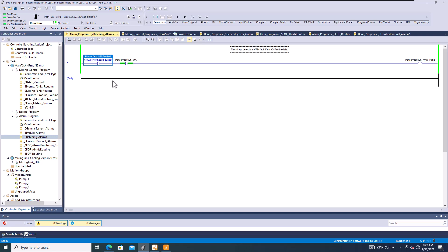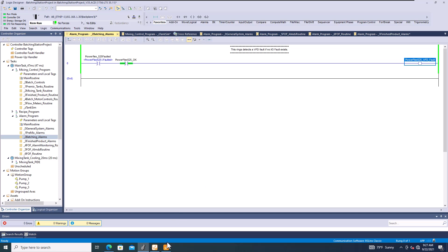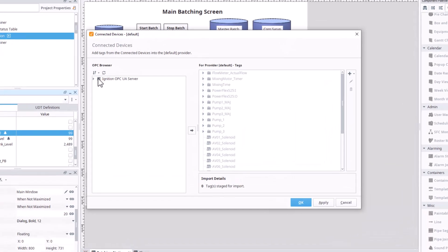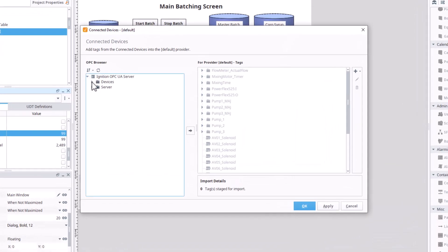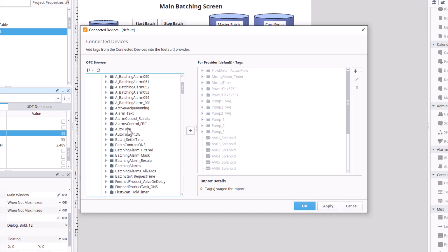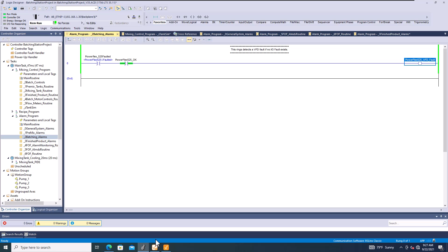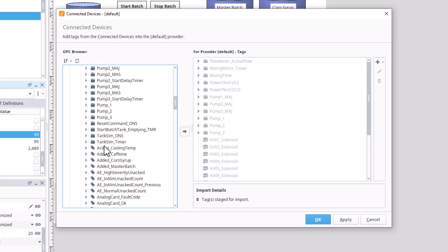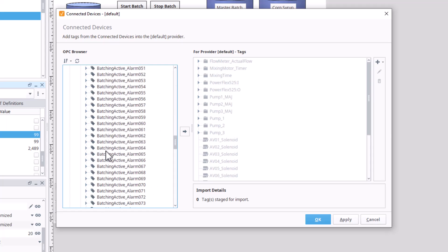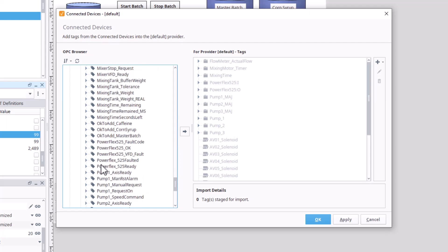Adding a drive fault alarm is just a matter of adding a tag. Browse to Ignition → our devices → batching station → global settings → batching alarms, and find the PowerFlex 525 VFD Fault tag. Add that into our system.